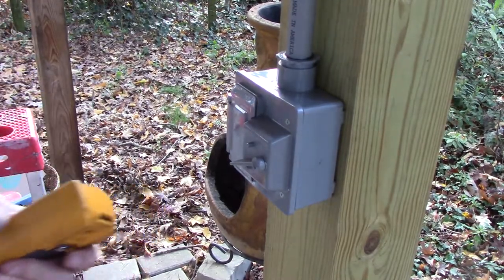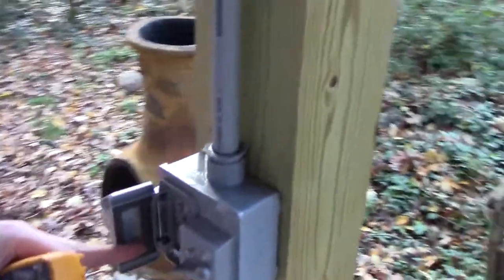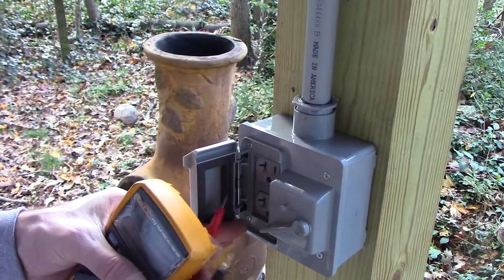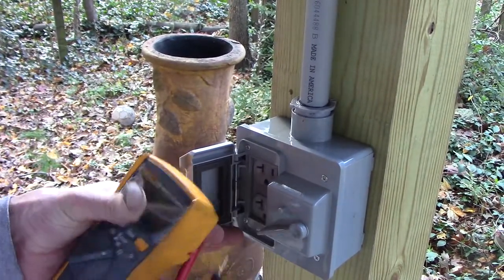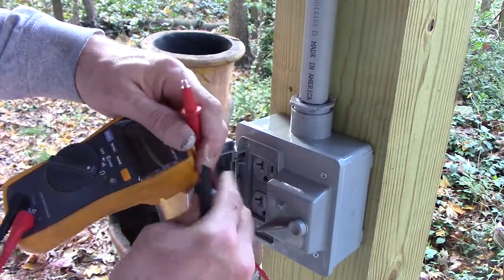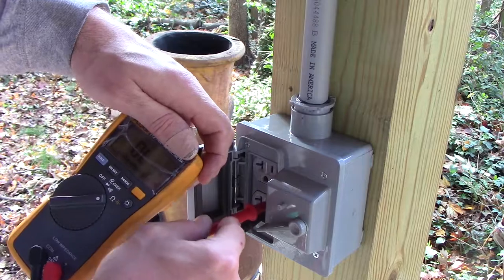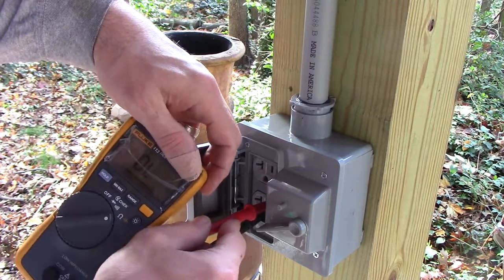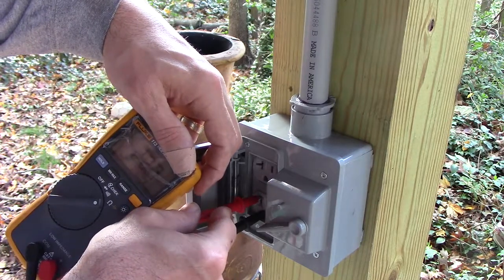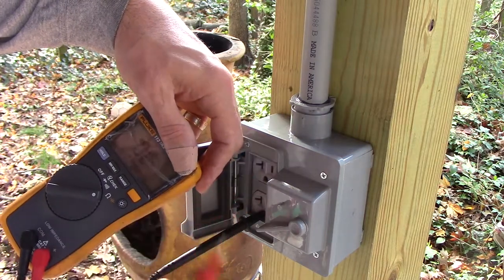Now that everything's connected we can do some basic tests to make sure we don't have anything screwed up. With the meter set on resistance, we put the black lead in the ground — we should be able to read no continuity on the hot side, open. And over here on the neutral, we should read about no resistance, which we do — like one ohm. So it shows it's grounded.